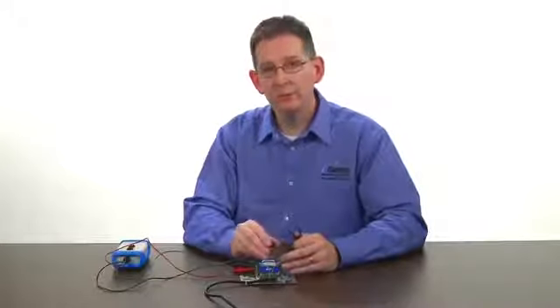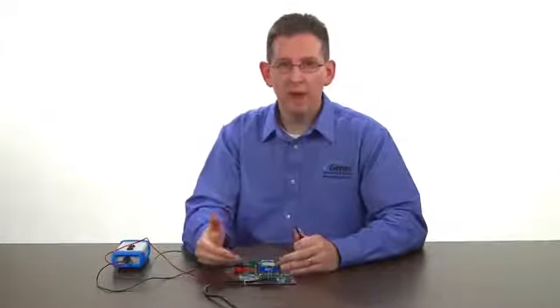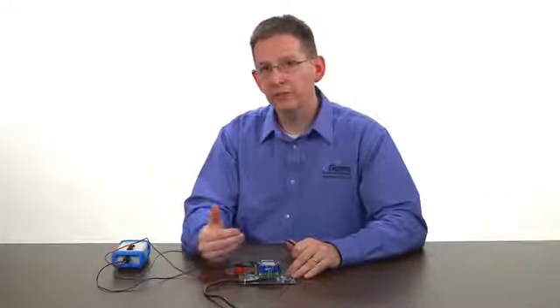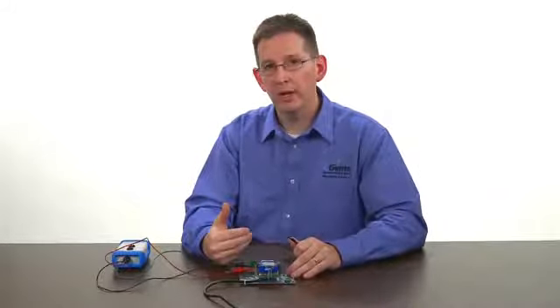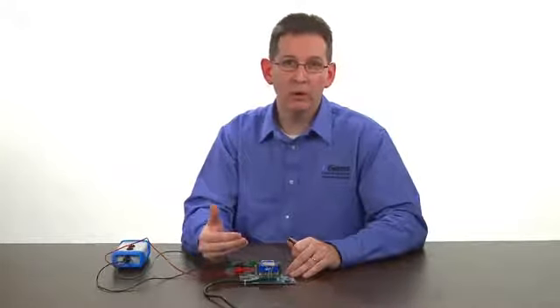This again is a direct mode unit. Should you have an inverse unit the actions are opposite. Meaning that the relay is energized when both probes are dry and de-energized when both probes are wet.